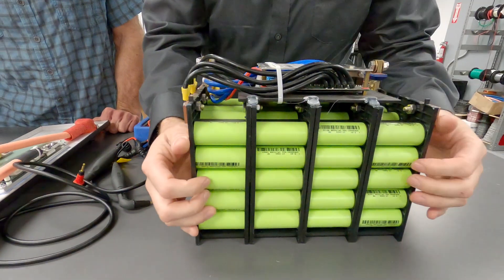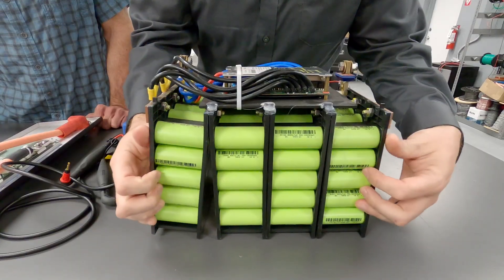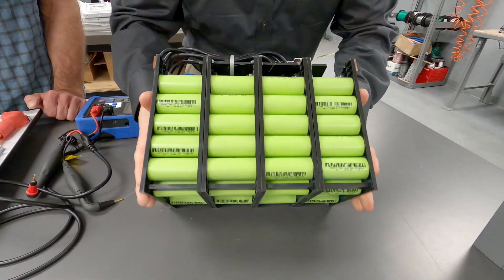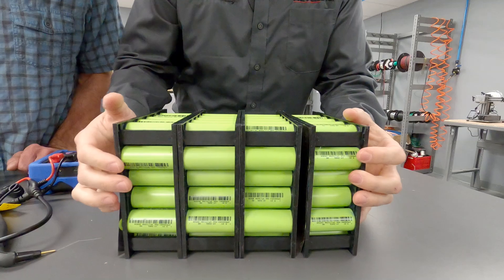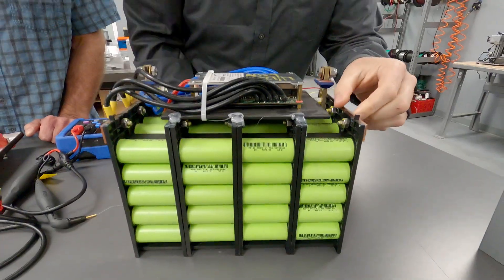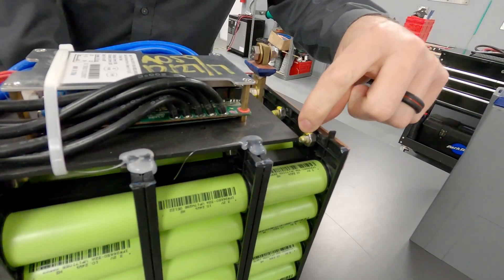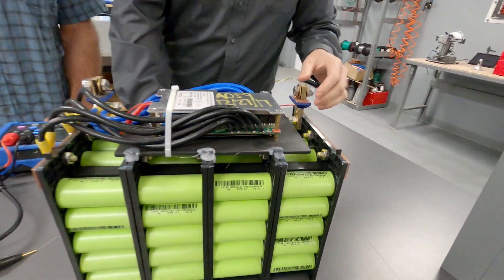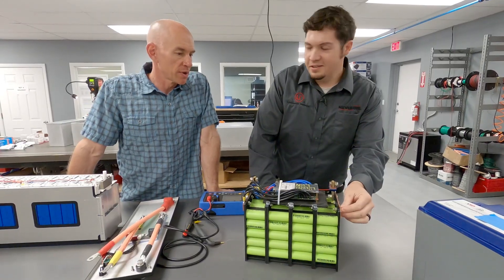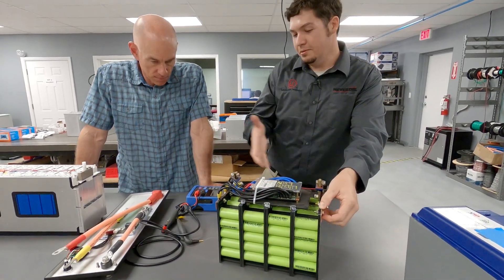These are assembled in blocks — each one of these blocks is 3.2 volts, and then four in series to get 12.8 volts nominal. What we see in these kind of constructed batteries is the amount of failure points is high, and there are some strange assembly methods — there's a load-bearing surface that's a conductive pathway with plastic in between, and that's a big no-no. You don't put plastic on something that might get warm because plastic yields under pressure, it's going to deform, you'll lose torque on the bolt, get higher resistance, more heat — a thermal runaway kind of event.